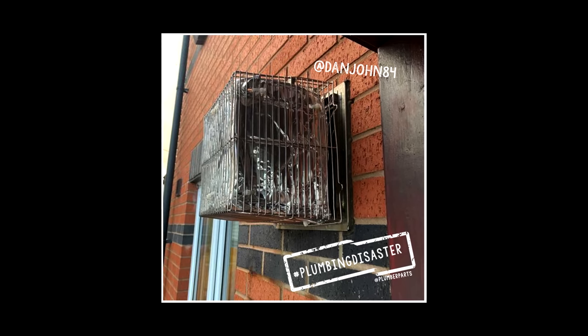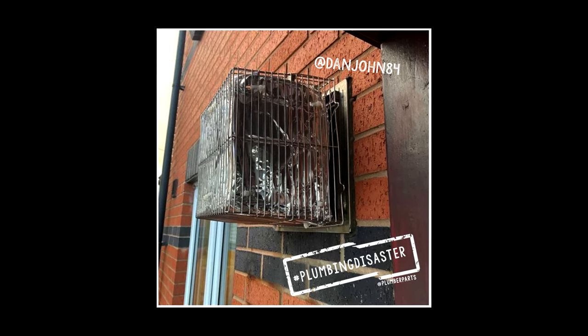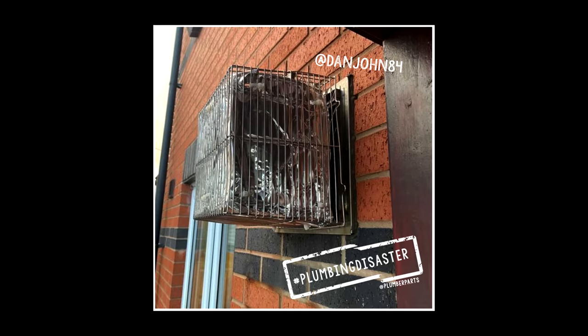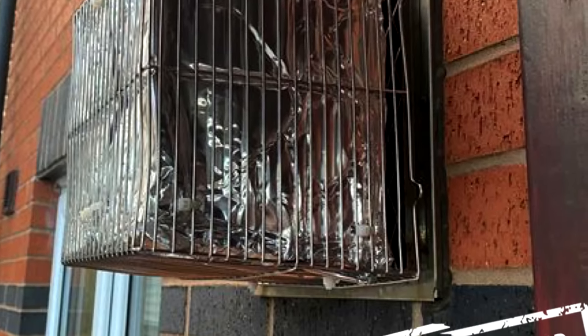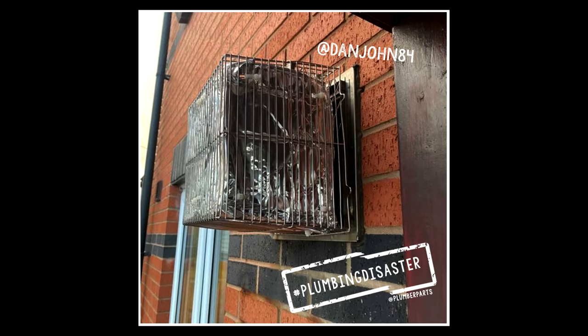At 15, DanJohn84 sent us in this little ditty. Customers can do some interesting things. Dan was there to quote for a new boiler as the pilot light kept going out. The customer did this to stop it being blown out — cover the flue, why don't you? Kill yourself, why don't you? Safe to say that Dan took that away. Guys, do not cover up any flue outlets. Always speak to a qualified oil or gas engineer.